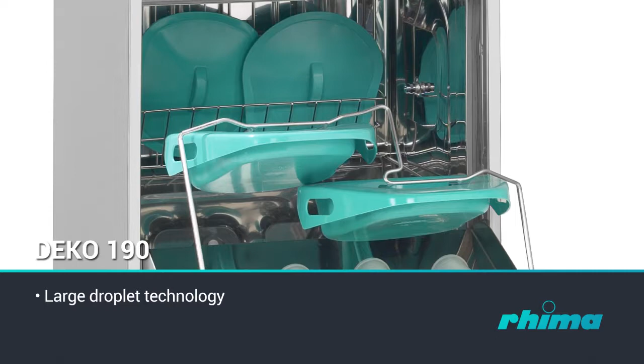The DEKO 190 automatically flushes, washes and disinfects bedpans and lids, urine bottles, hand wash basins, suction bottles, kidney bowls, theatre overshoes, vases and even floor cleaning discs, plus all other reusable products used for similar purposes within patient care. It pre-washes instruments prior to CSSD, eliminating exposure due to manual handling. It is important to note, the DEKO 190 is the only machine that washes, cleans and disinfects itself after every cycle.